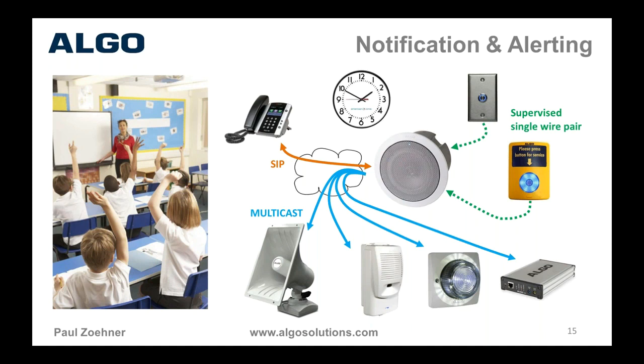It could be a SIP call from the phone to one of the devices, which will then play a WAV file and multicast it out to any of the devices that you want based on a zone. You can have that button directly input to a speaker. So if you had a horn speaker, for example, in a manufacturing facility, you could use that blue and yellow button tied into that horn speaker, and when you push the button, that horn speaker will play a WAV file, maybe over that horn speaker or maybe over different speakers in the environment, or through the IP adapter to legacy infrastructure that's already in place. You can also activate the strobe lights, so there's all sorts of ways to put it together, and of course it could be time-based with the 8301, which is the purpose of the clock here.